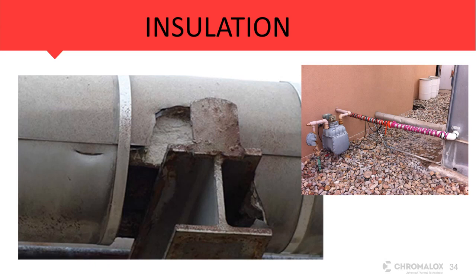Same thing on the top, you see a valve's missing here. I mean, a blanket's missing on this valve. If you're going to cut and cope, you've got to make sure that you go back and do it properly and seal it up. In this case, water can still get in here. We can get the ingress of water. This is not properly sealed off. This could be an issue for us whenever it gets really, really cold.